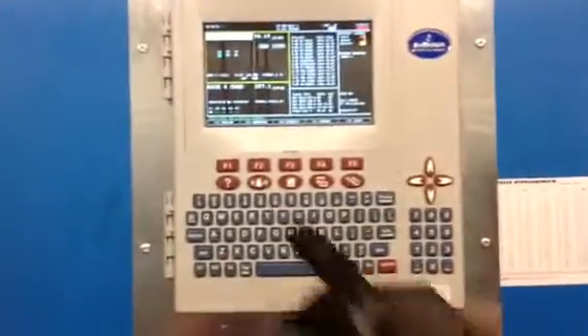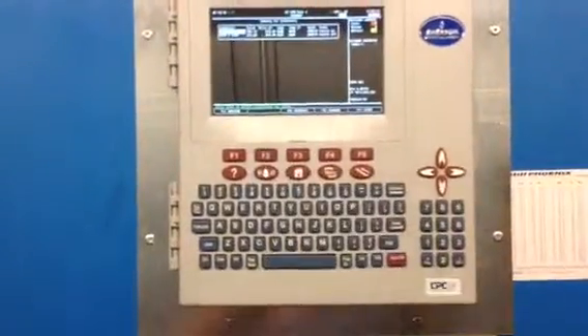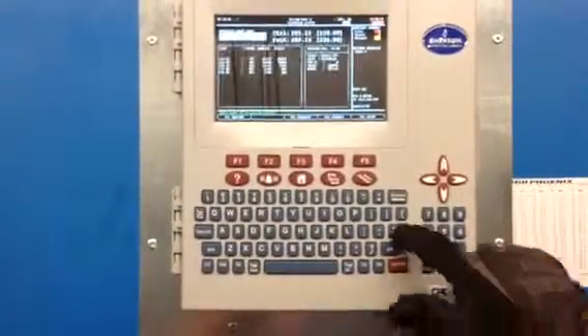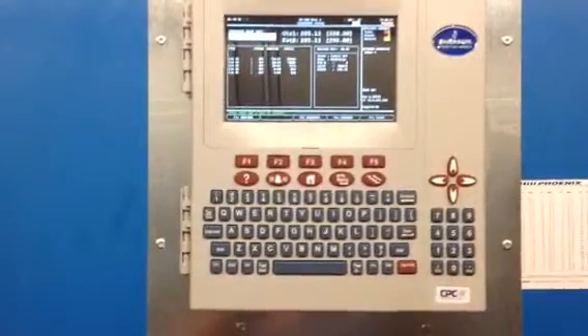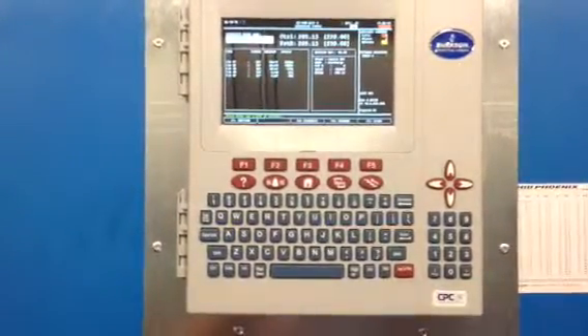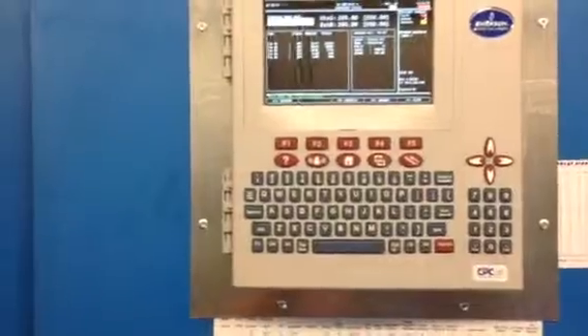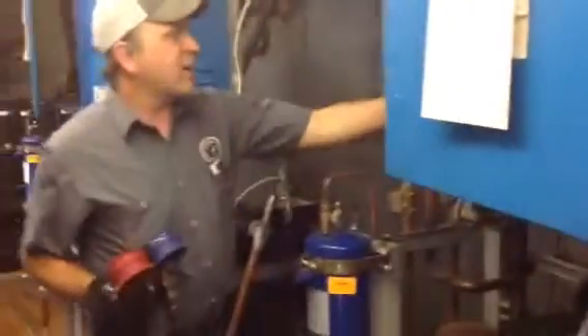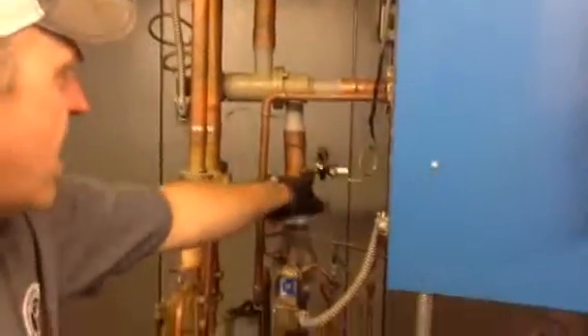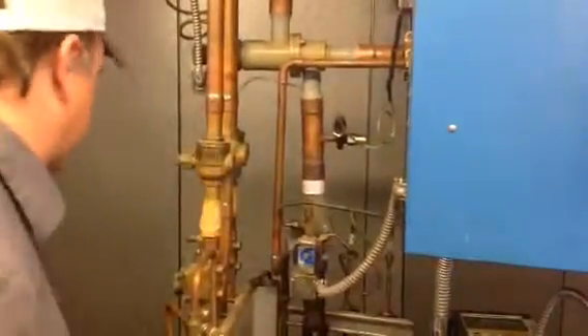Now we have a discharge transducer to calibrate. So we want to go back to home, condenser, rack 4, enter. We're showing 205 pounds. So let's go find our discharge transducer, which is located just underneath the split valve. Right above the BDR, here's our discharge transducer.